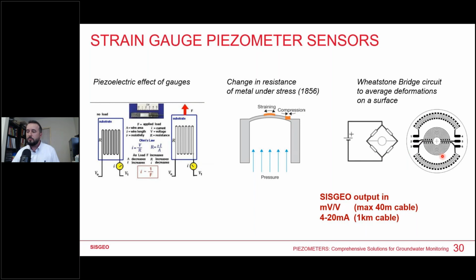Applying this principle on the diaphragm, the diaphragm is basically a sort of coin made in ceramic. This coin has a circuit of copper print on it, and by means of a Wheatstone bridge circuit, we can average the deformation on the surface, because you have strain and compression at the same time here. Then the output, or the signal that comes out, can be directly the Wheatstone bridge in millivolt per volt, but with it, you are limited to a certain length of cable because the signal is very small. Or we also use a transmitter, a converter, in order to enhance the signal up to 1 kilometer, even more. And this signal is made in 4-20 milliamps.